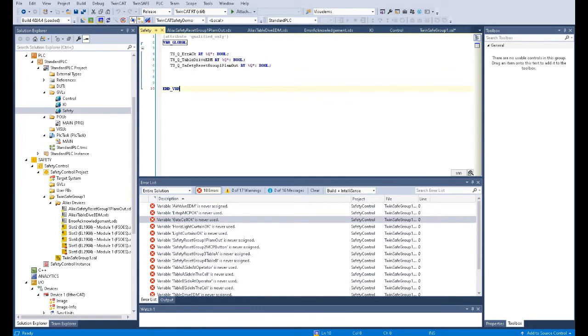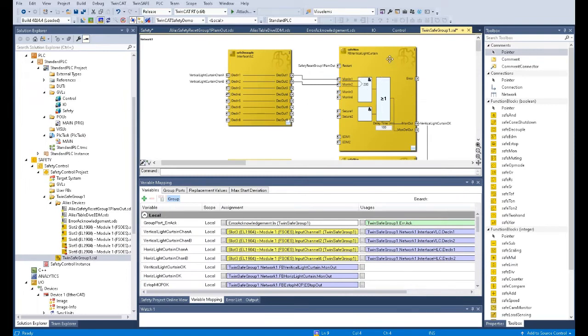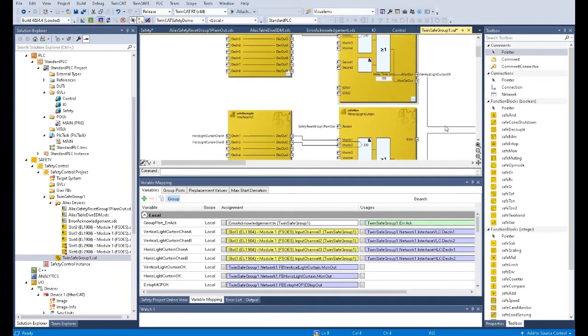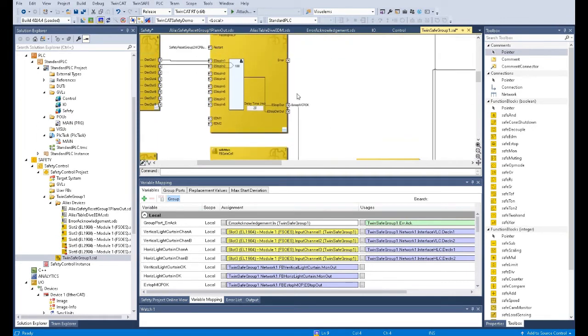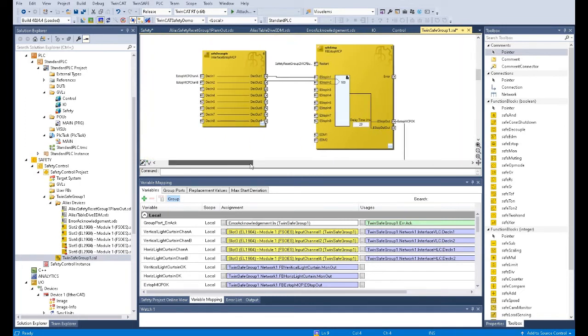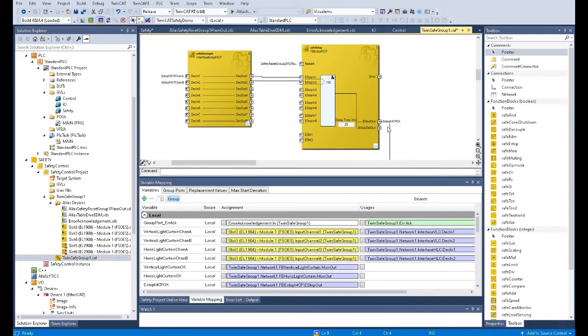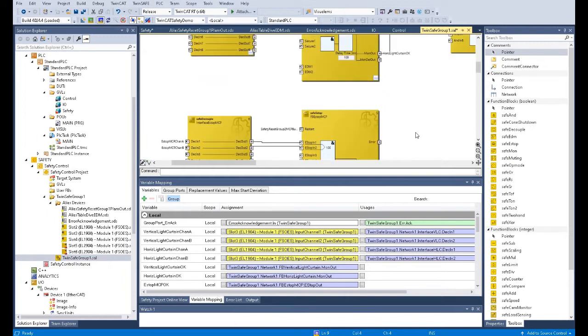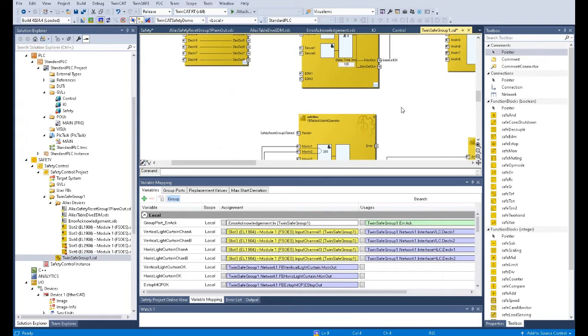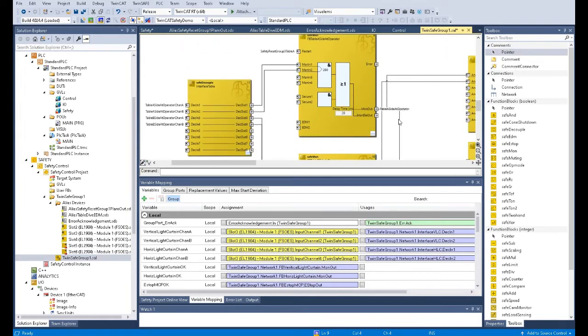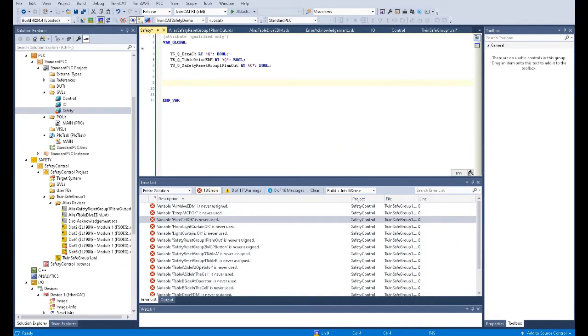Those are the three signals coming from the standard PLC. We also have some signals that need to be transferred from the safety PLC to the standard PLC. For example, for each function block — vertical light curtain, e-stop MCP — the HMI needs to show the light curtain status, e-stop status, gate status, and table switch signals. These signals need to be used as normal signals shown on the HMI. So let me show how we can do that. Go to the safety side and let's create three typical signals here.